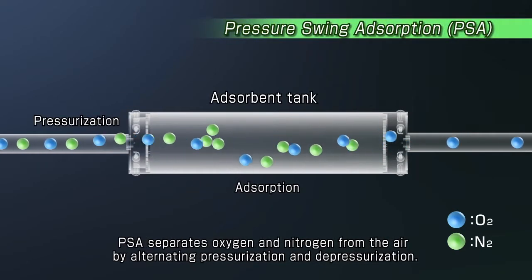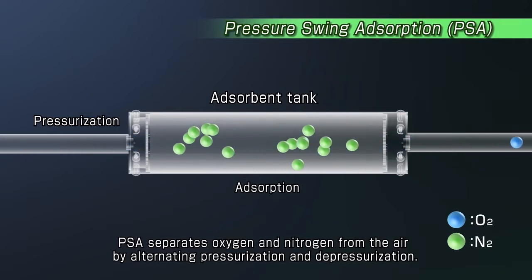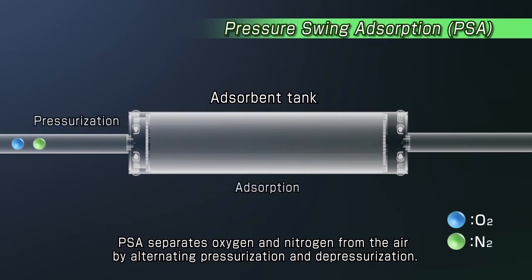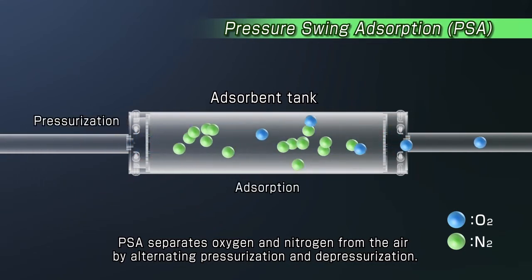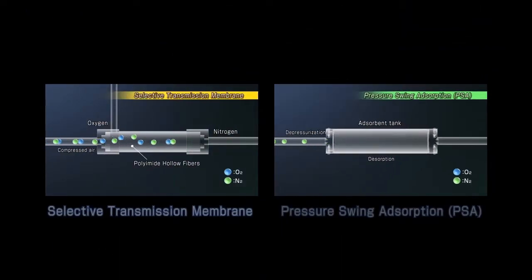Pressure Swing Adsorption Technology is utilized to adsorb nitrogen at high pressure. The process then swings to low pressure to desorb the nitrogen. Daikin developed its original Vacuum Pressure Swing Adsorption, or VPSA, technology based on pressure swing adsorption.